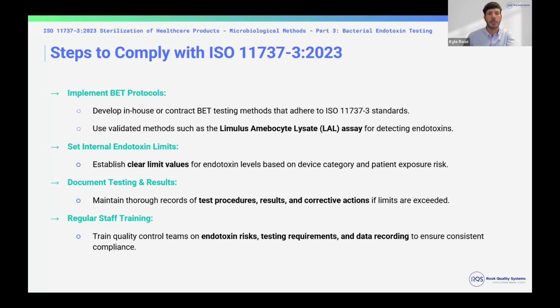So developing an in-house or contract endotoxin testing method. Ensure that you have a validated method such as the LAL assay for detecting endotoxins. Establishing clear limit values for this based on your device and patient exposure risk, and maintaining these records through your testing. One key thing that we've worked with our clients on, and slightly different than biocompatibility, is this endotoxin testing is related to actually manufacturing.